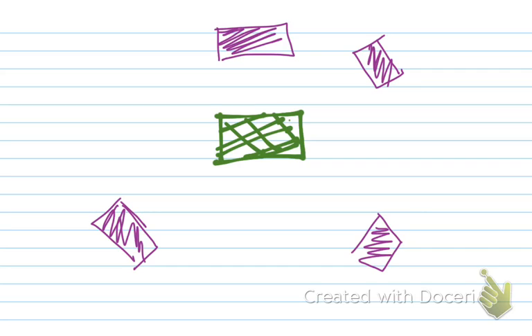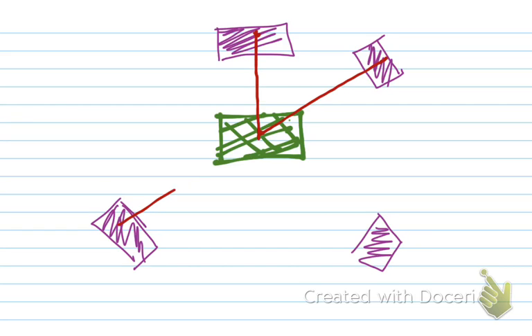The perpendicular bisector method states that first you need to draw straight lines connecting the existing substations and the proposed substation. Draw straight lines from all the existing substations to the proposed one. The next thing you're going to do is bisect these lines perpendicularly.